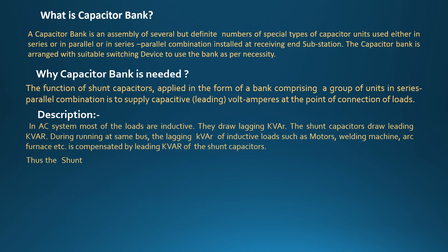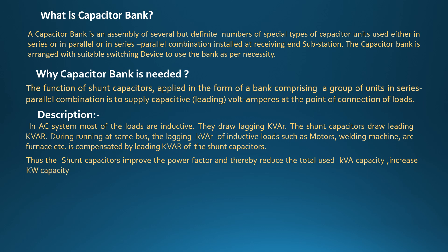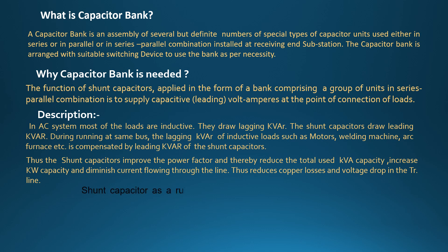Shunt capacitors improve the power factor and thereby reduce the total used KVA capacity, increase KW capacity, and diminish current flowing through the line, thus reducing copper losses and voltage drop in the transmission line. Shunt capacitors are as a rule connected near the load end and also at the receiving substation.